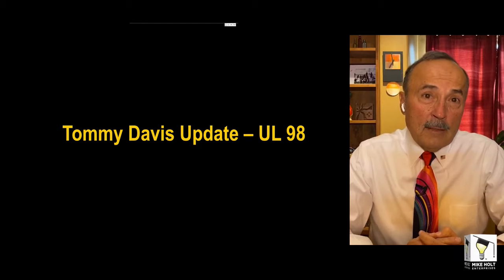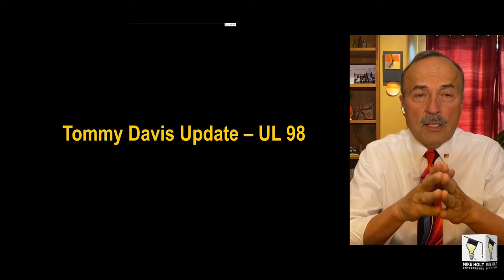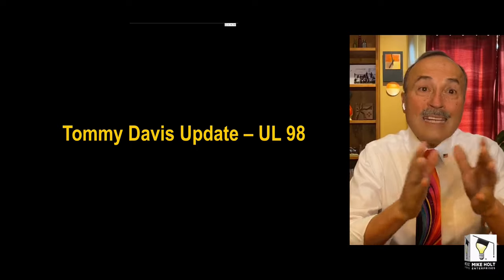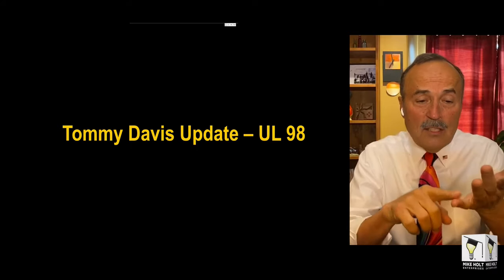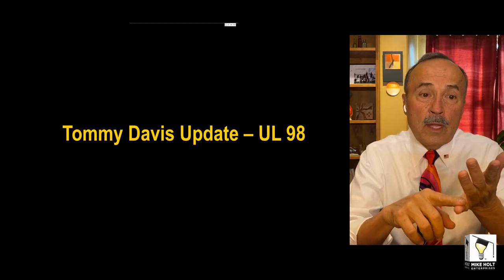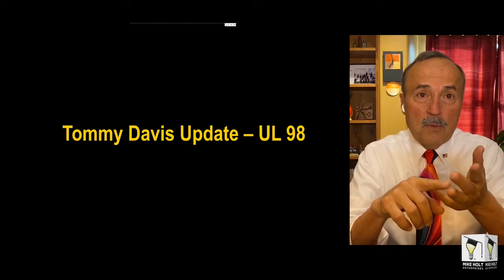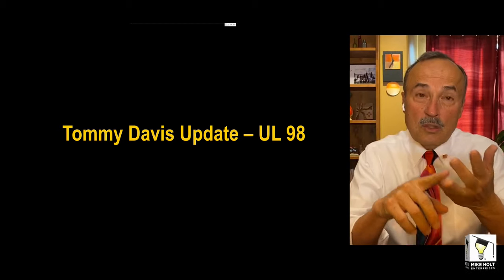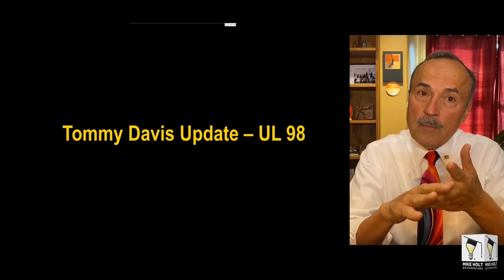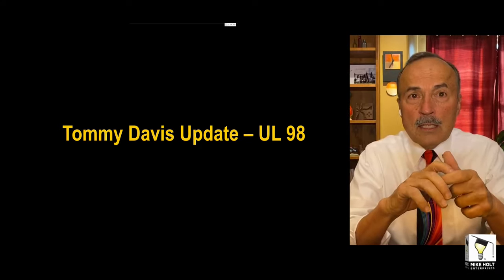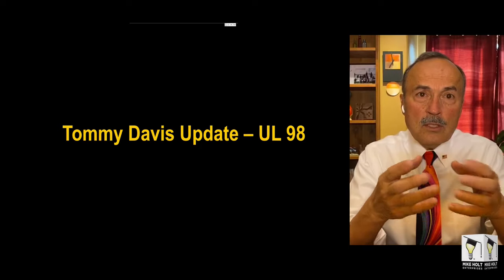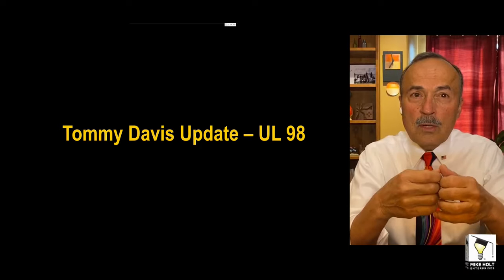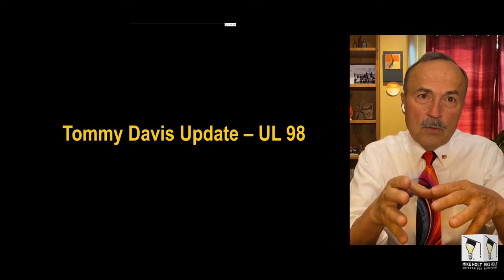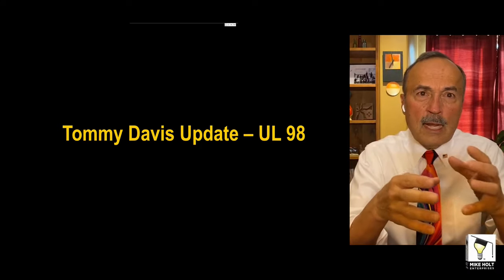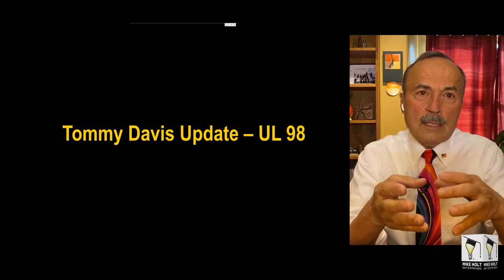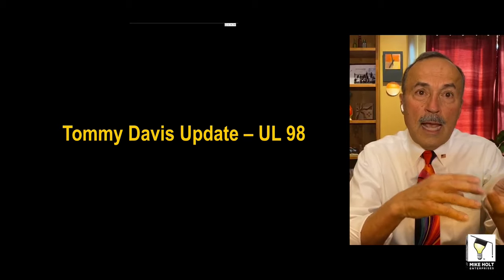So now there was an update, and Tommy said that he actually submitted some information to UL to change the product standard. I mean, this guy, he changed the Maryland law. He gave so much crap to people in the electrical industry that somebody thought it was a good idea. The 2020 code changed it, but only for solar. And then he went to UL and said, listen, we need to have some kind of mechanism so this door can't just be opened up without a tool. So UL is looking at this proposal that he submitted, and I forgot what the language was called, where they want to coordinate this with Mexico as well as Canada.